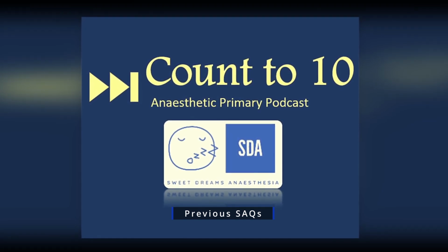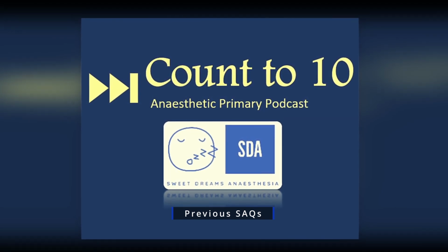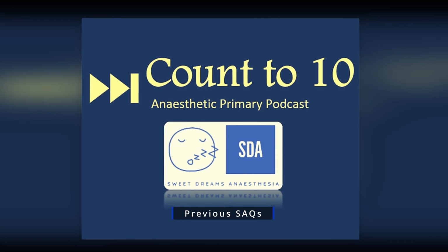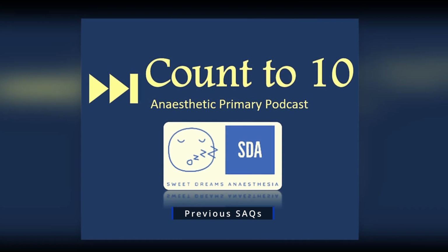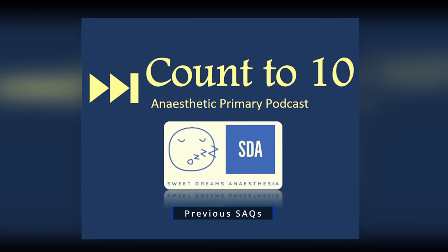You can also do a spectral edge frequency, where if you drew a line where underneath it 95% of the waves were under this line, where will that line lie? And then finally, you can look at those waveforms and see if there's anything called bicoherence, i.e., in my head what this means is, do those things look like they have synchrony or are they out of sync? If they're in sync, they have increased bicoherence, and if they're out of sync, they have less bicoherence. Using all those types of domain analysis, that's how the BIS ends up giving you a number and a processed EEG to look at.